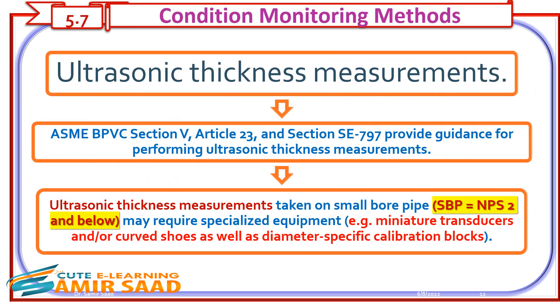Condition monitoring methods using UT and RT: ASME B&PVC Section V, Article 23 and Section SE-797 provide guidance for performing ultrasonic thickness measurements. Ultrasonic thickness measurements taken on small bore pipe may require specialized equipment — for example, miniature transducers and/or curved shoes as well as diameter-specific calibration blocks.